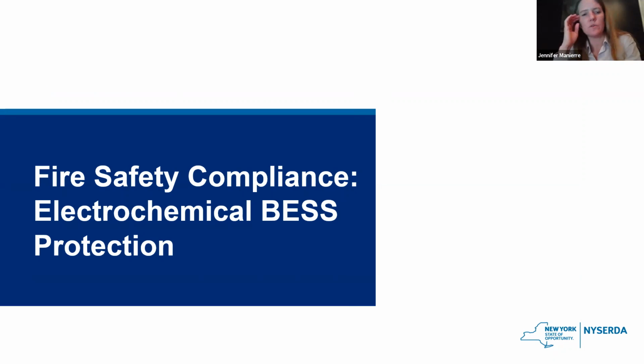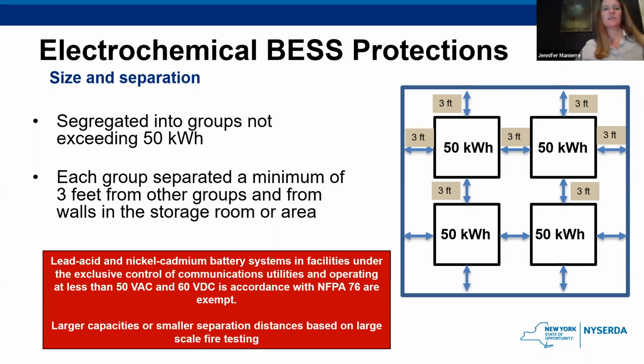Okay, so now we're going to start talking a little bit about electrochemical storage system protections that are required based on the location of the system, which we'll discuss a little bit later. Okay, so some of the electrochemical energy storage protections, in particular, size and separation. They need to be segregated into groups that do not exceed 50 kilowatt hours each. And each of those groups of batteries needs to be separated by a minimum of 3 feet from other groups and from walls within the room or area.